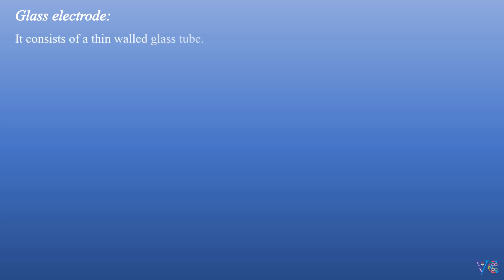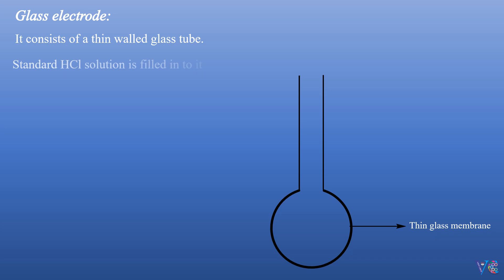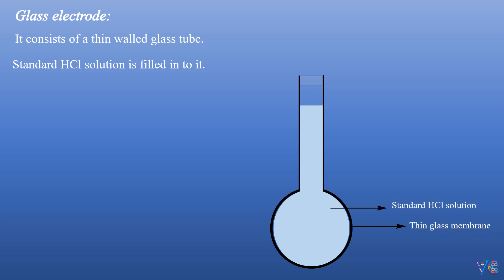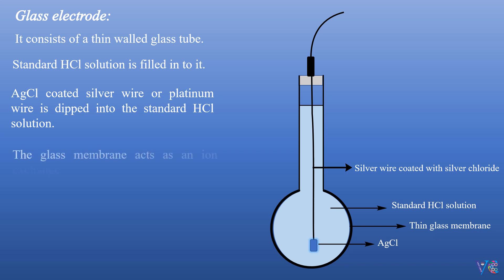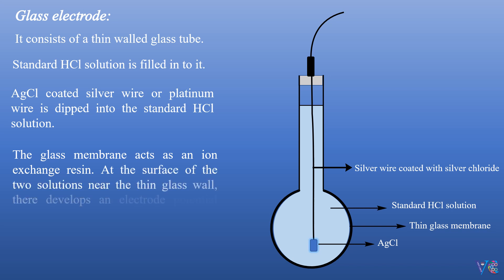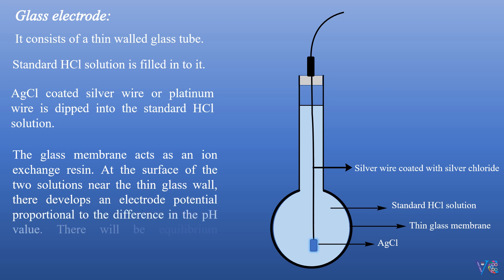The glass electrode consists of a thin-walled glass tube. Standard HCl solution is filled into it. A AgCl-coated silver wire or platinum wire is dipped into the standard HCl solution. The glass membrane acts as an ion exchange resin. At the surface of the two solutions near the thin glass wall, there develops an electrode potential proportional to the difference in the pH value. There will be equilibrium between the Na⁺ ions of the glass and H⁺ ions in the solution.